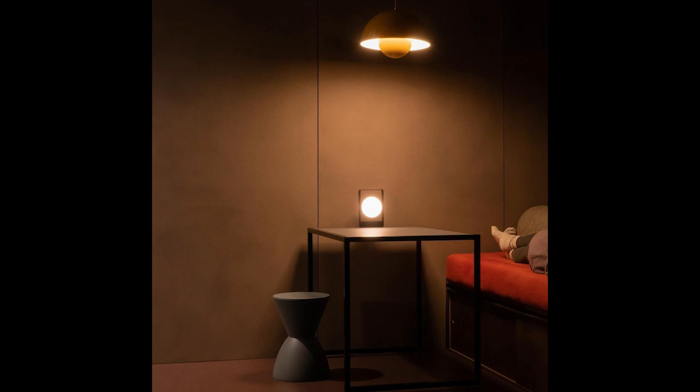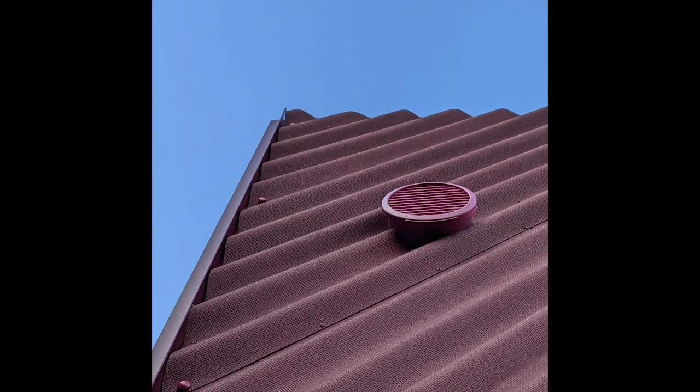And then the key consideration with that is how do you get your fresh air? So you have to have some form of mechanical heat recovery to do that. But mechanical heat recovery you'd normally associate with quite a big house or larger commercial building. So we actually found a product called Lunos, who do a decentralized mechanical heat recovery system. You end up with two. They look a bit like a regular bathroom fan, that sort of size, but they work together. There's a pair of them, and they have a ceramic heat exchanger in the middle.